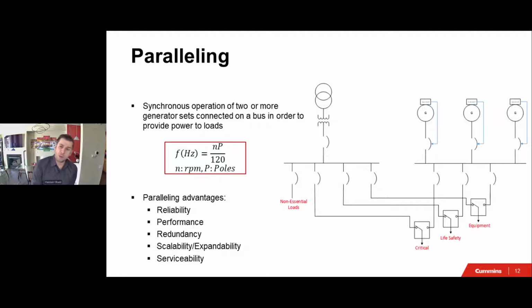You might ask the question, even though the discussion is about paralleling, why you wouldn't want to parallel. I would say the number one reason is cost. You don't want to add another generator if your application doesn't need it. Obviously, if it's a hospital, critical infrastructure, or a data center, yes, you would want to specify redundancy. But for example, if we have a generator for a grocery store or maybe a discount retailer, we probably don't need multiple generators in parallel to feed that load. So it really depends on the application. But really, there's no downside to paralleling generator sets.